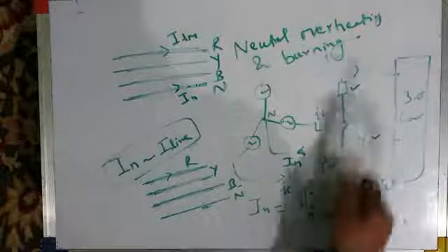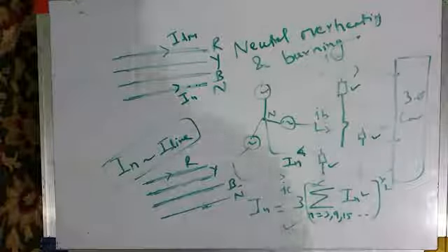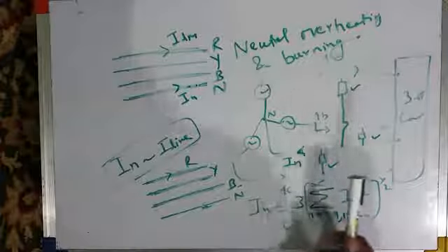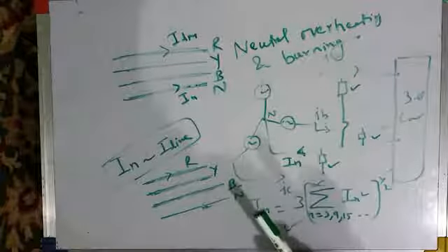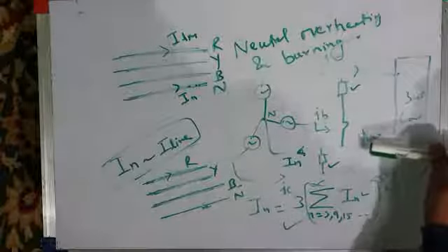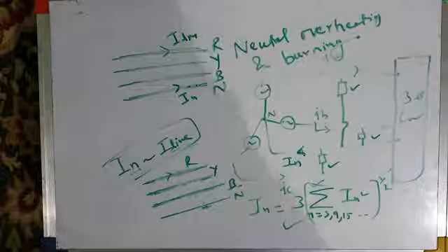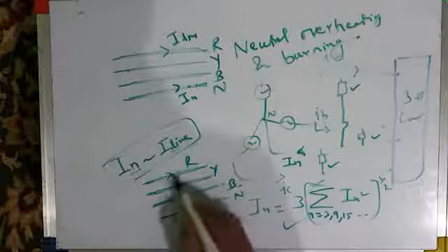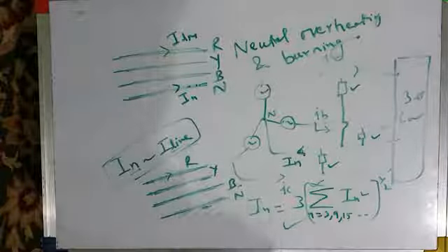Because single-phase non-linear loads, which are used in commercial establishments, shops, offices, hotels, cinemas, and in our homes, result in the flow of strong triplen harmonics, and those triplen harmonic currents flow in the neutral, and they make the neutral current very nearly equal to line current. After that, engineers understood that the neutral conductor should be as thick as the line conductors, and that solved the problem.